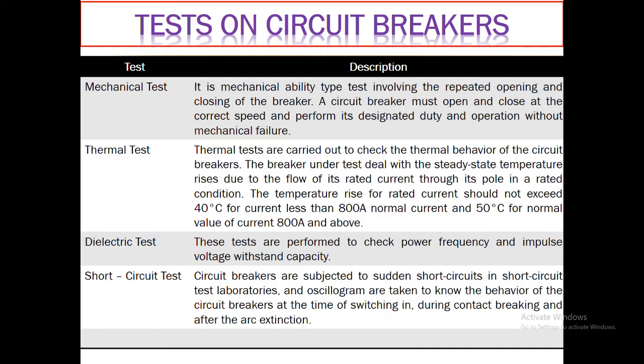If the circuit breaker contacts are moving at a very slow speed, then again it will be a drawback for the circuit breaker. So when we are performing the mechanical test by opening or closing, one has to monitor the time of opening, time of closing, speed of opening and speed of closing, and check whether the separation and closing performance proceeds as per its designated duty or not.